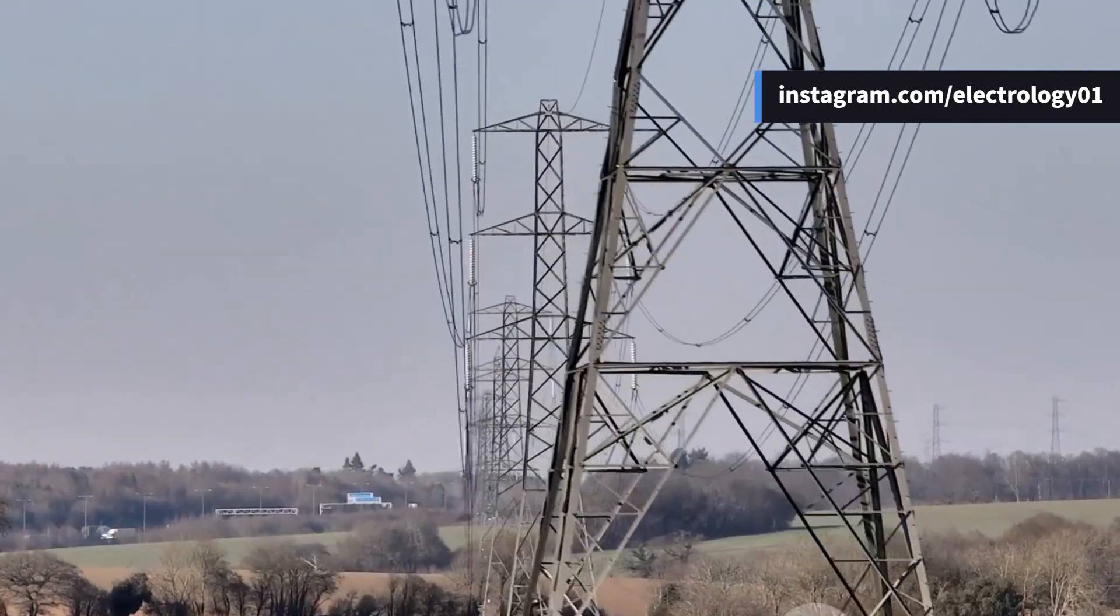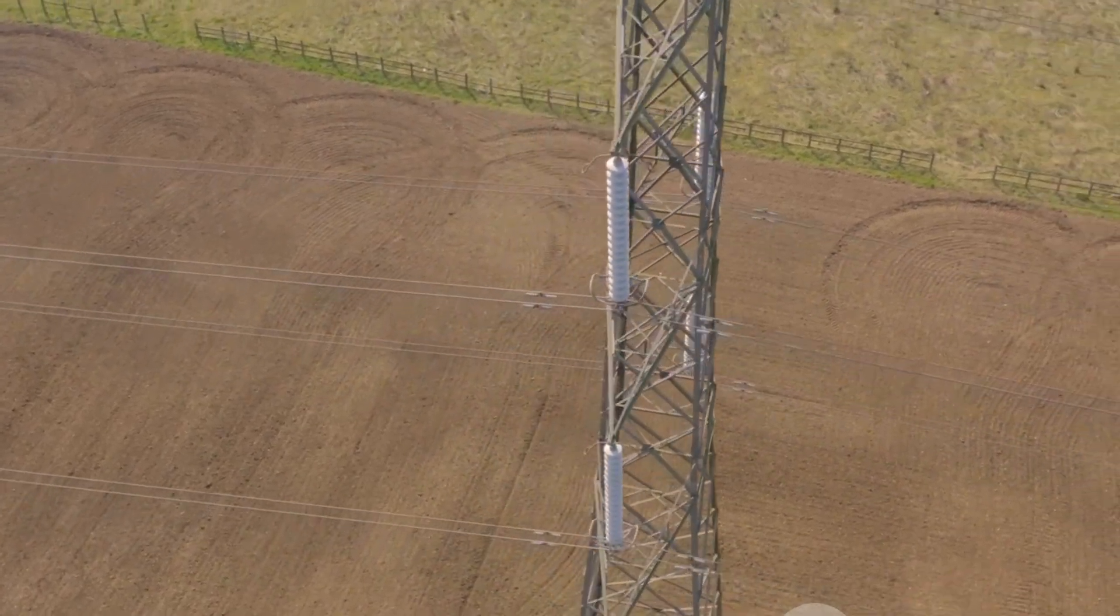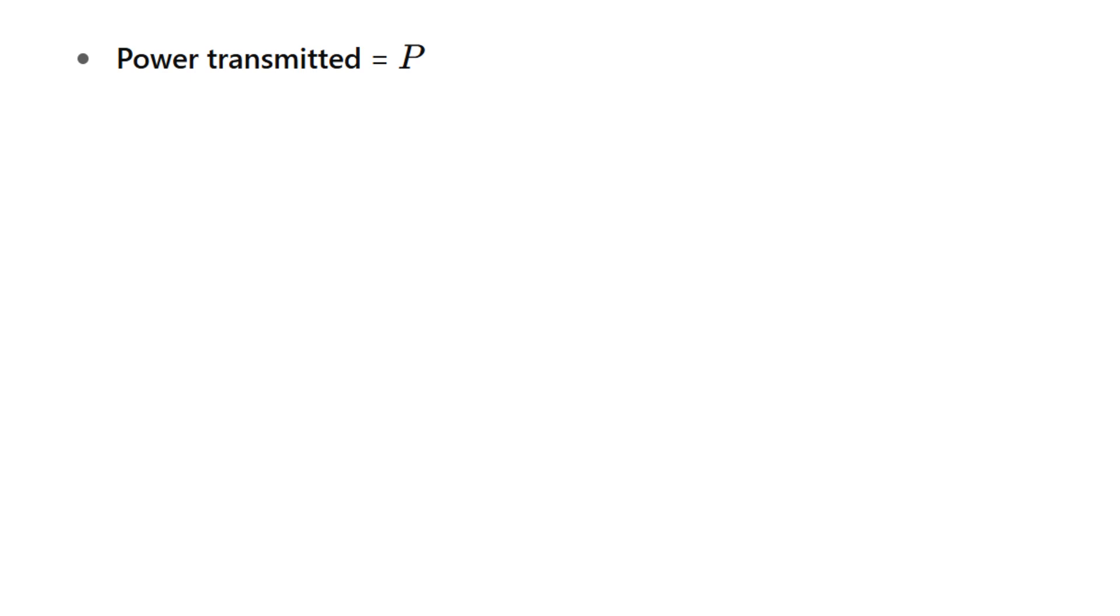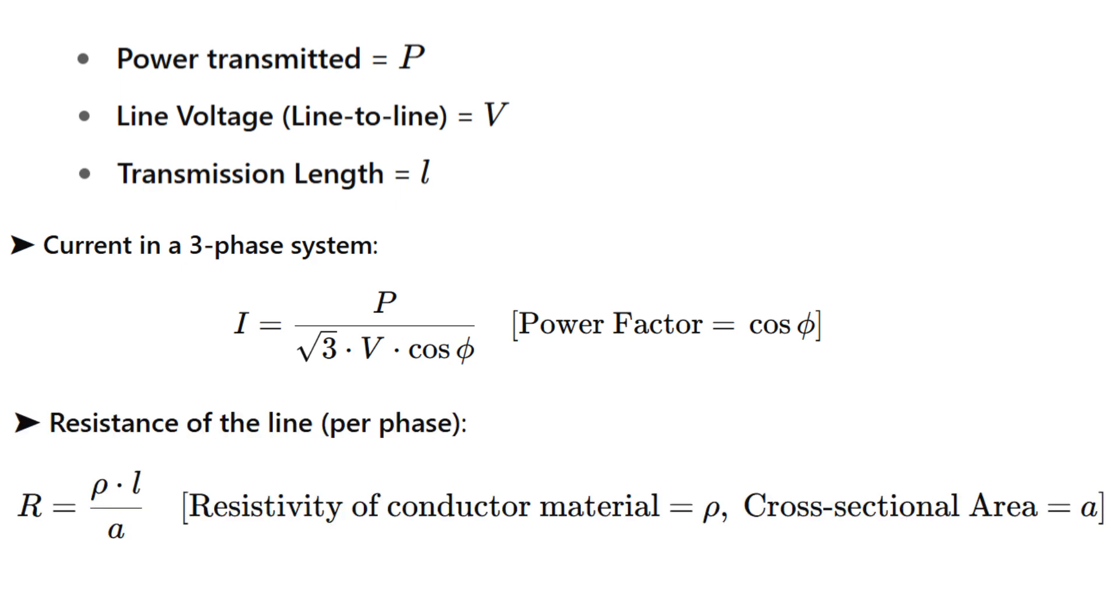First and foremost, high voltage reduces the volume of conductor material required. Let's understand this with a bit of math. Suppose you're transmitting a certain amount of power denoted by P at a line voltage V over a length L. Now the load current I is given by I equals P divided by root 3 times V times power factor.